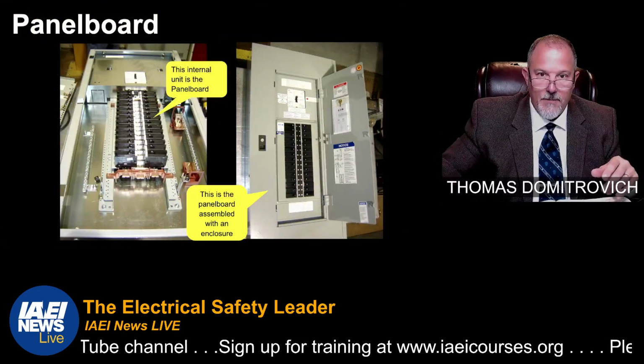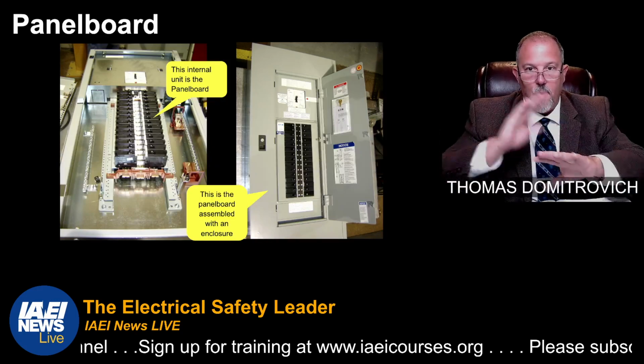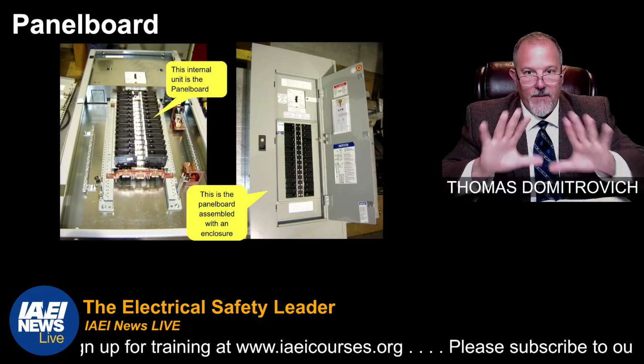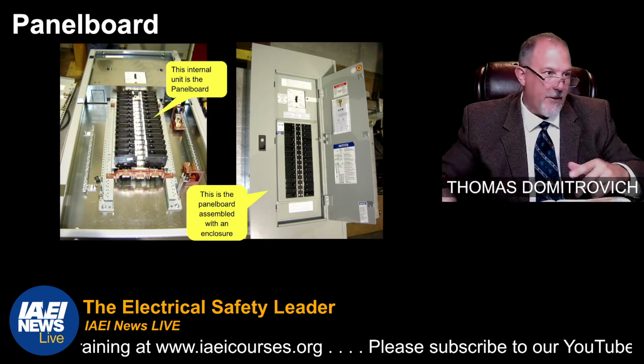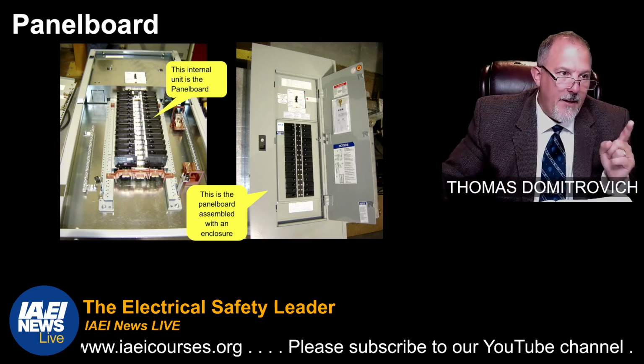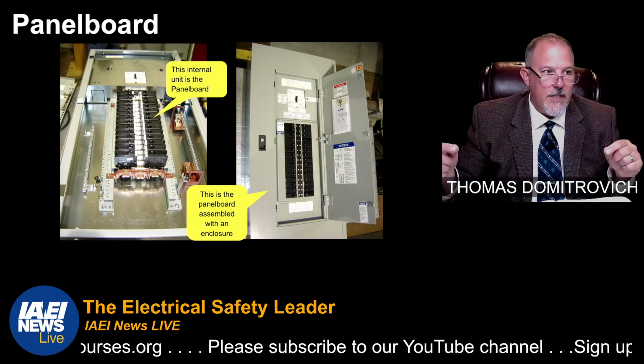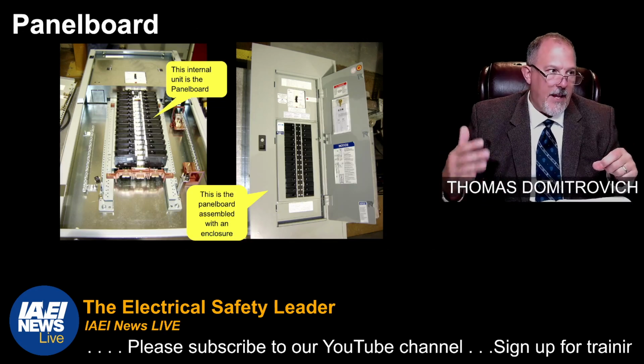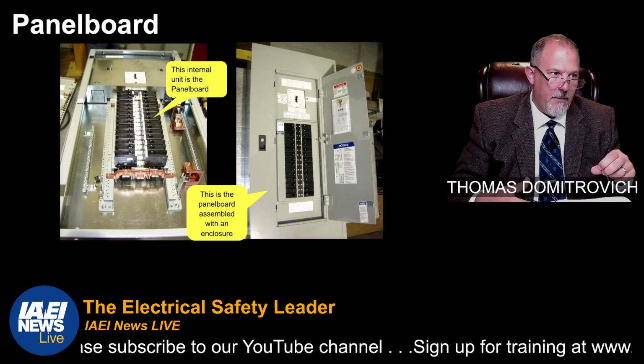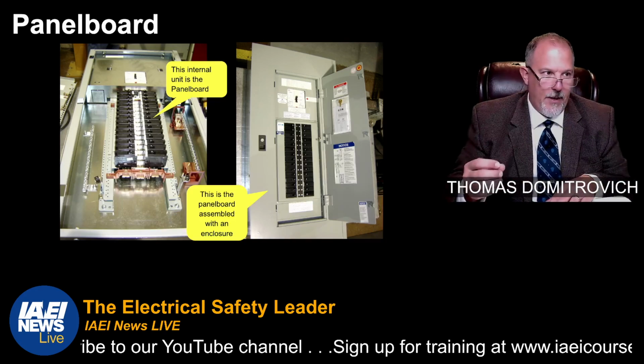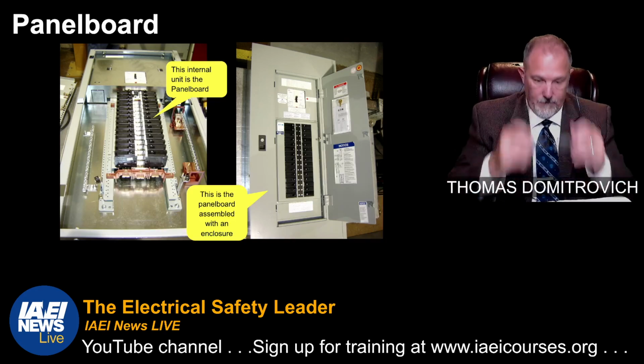That's the dead front piece. When you open that outer door, you have a dead front that's going to keep you from touching anything energized. They added, when the available fault current is greater than 10,000 amps, the panel board and enclosure combination have to be evaluated for the application.